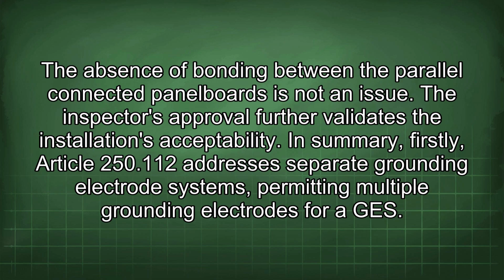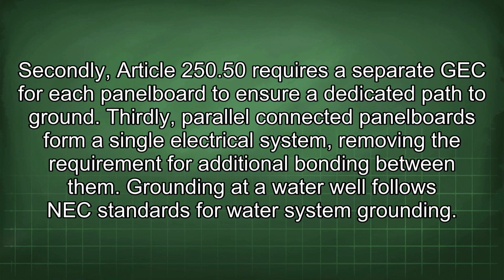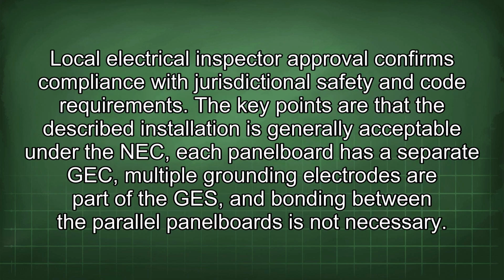In summary, firstly, Article 250.112 addresses separate grounding electrode systems, permitting multiple grounding electrodes for GES. Secondly, Article 250.50 requires a separate GEC for each panel board to ensure a dedicated path to ground. Thirdly, parallel connected panel boards form a single electrical system, removing the requirement for additional bonding between them. Grounding at a water well follows NEC standards for water system grounding. Local electrical inspector approval confirms compliance with jurisdictional safety and code requirements.